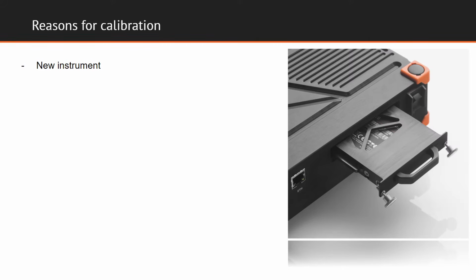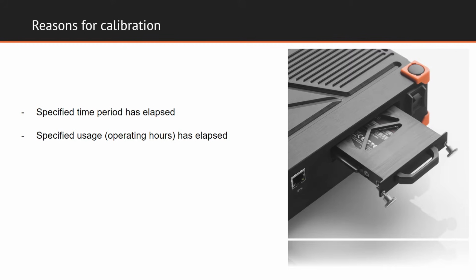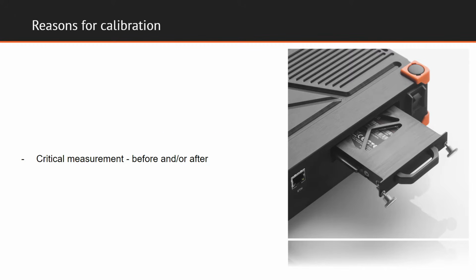But generally speaking, calibration should be performed in the following situations. When we acquire a new instrument that has not been utilized before, for example, and after each repair or modification that has been carried out on the measurement equipment, in the event of a specified time period or specified usage in operating hours having elapsed. Furthermore, it's a good idea to carry out calibration before and after a critical measurement in order to ensure that characteristics of the system remain the same during that critical measurement.